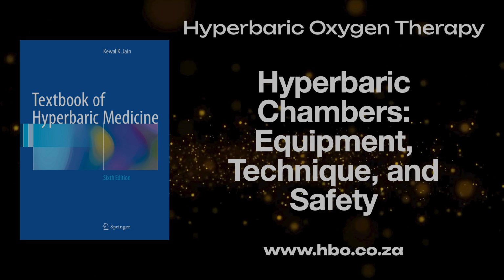Sure. Monoplace: the whole chamber fills with 100% oxygen from the start. You just breathe the air inside. Right. Multiplace: the chamber pressurizes with regular compressed air. Once at pressure, patients put on tight-fitting masks or hoods to breathe the 100% oxygen.